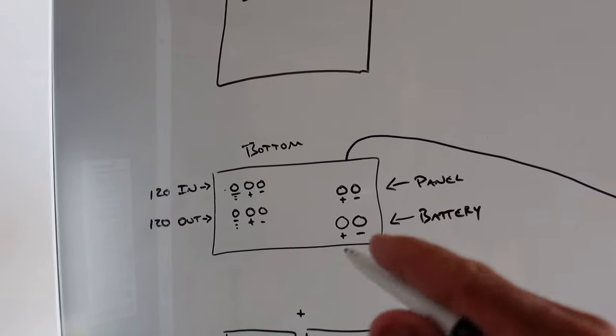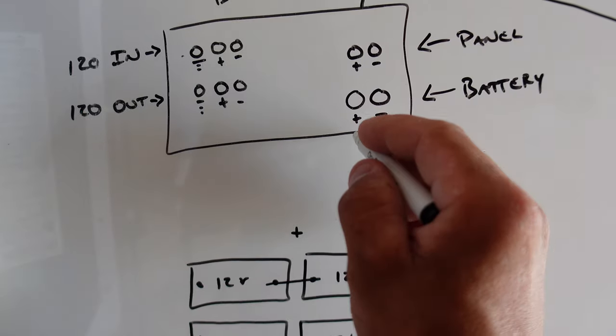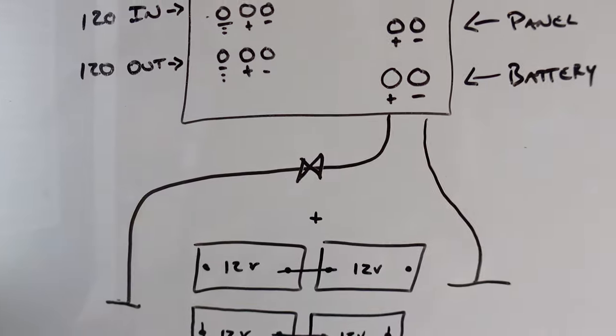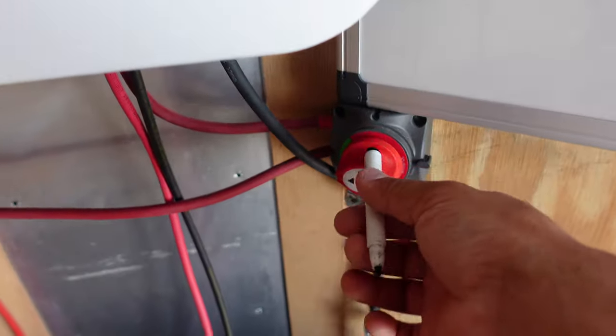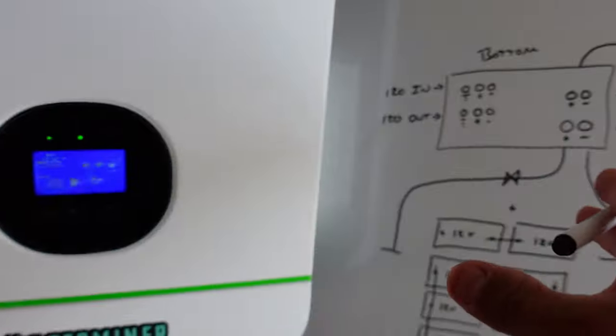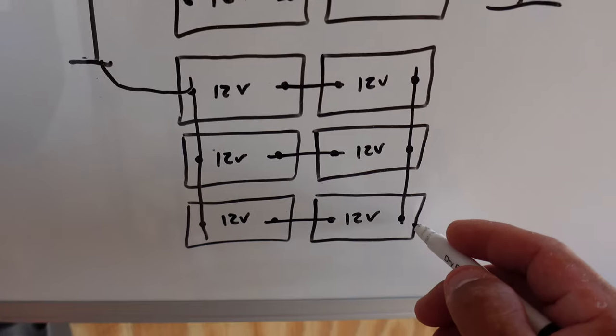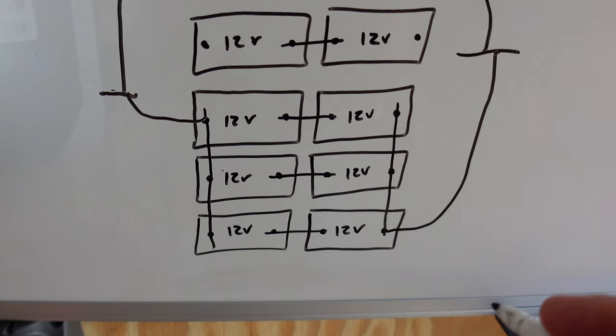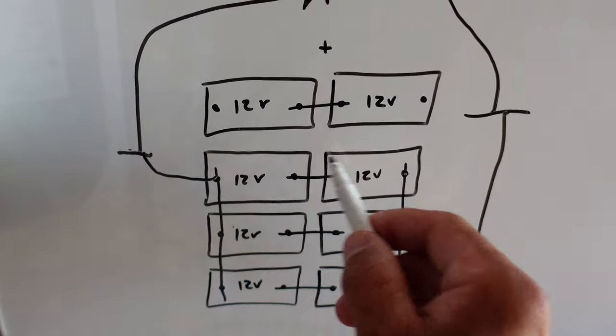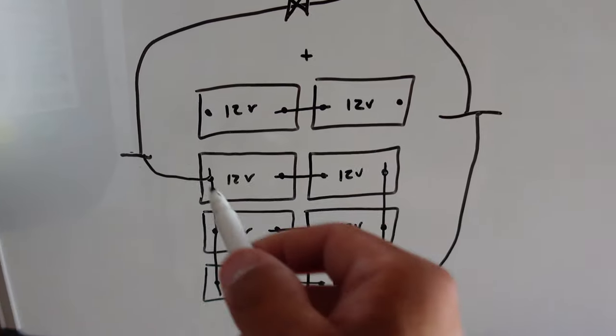Looking at the batteries, I have a negative terminal that comes down on this side of the batteries to a bus bar, then I have the positive that does the same thing, comes over here to a bus bar. We have a shutoff right here, this is the disconnect of the unit which is right here, to be able to discharge or shut off the circulation of power so we can isolate the unit to work on it and just not have power to it. We have the lead coming from this top battery over here going into this bus bar, and the bottom over here negative goes into this bus bar. The reason for this is because you want the power to disperse evenly across all of the batteries and not just from here to here, because then it would just be looping through the top set of batteries theoretically, not fully through all of them evenly. So that's why you do the diagonal connection.